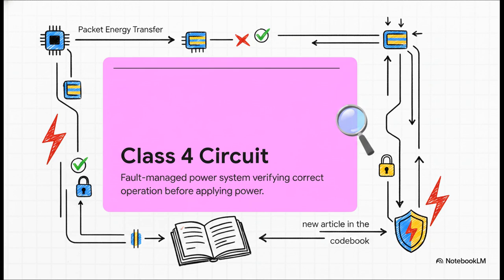Okay, here's where things get genuinely futuristic. Let's talk about the Class 4 circuit. People often call this digital electricity or packet energy transfer. It's a fault-managed power system that literally uses software to verify the presence and correct operation of devices before it even lets power flow. If the software detects a fault, boom, it terminates the output power instantly. But because this level of protection relies entirely on software and listed equipment, rather than an electrician physically turning a wrench, it needed a completely new set of definitions, plus a whole new article in the codebook, to ensure it's deployed safely.